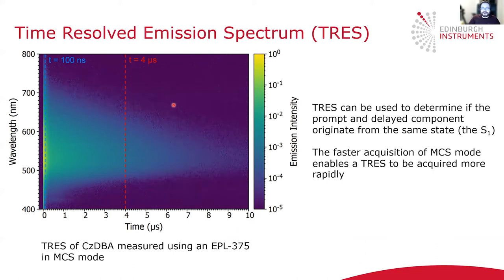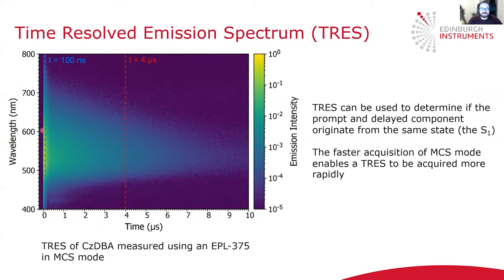Another measurement very useful for the characterization of TADF emitters is the time-resolved emission spectrum (TRES). This is where the photoluminescence decay of the emitter is measured as a function of emission wavelength. On the x-axis we have time — the time axis of the decay — and on the y-axis is wavelength. We can see a color plot showing how the decay varies as a function of wavelength. To acquire these TRES spectra, measuring the decay using the EPL in MCS mode is a big advantage, because these decays take quite a lot of time and MCS mode allows them to be acquired more rapidly.